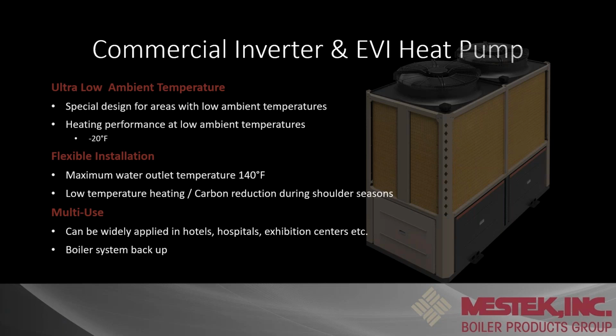It can be applied anywhere. It's basically just trying to match that load. It's going to depend on how many you will need, but hotels, hospitals, exhibition or exhibit centers, and we can also tie in a boiler as backup. I'm going to touch on that as well, but just think of these areas where they're saying, I have to reduce the carbon footprint. Does that mean you have to take the boiler out? No, that means we may add 2 or 3 heat pumps, and all of a sudden we're reducing carbon emissions. Keep that in mind as well. That doesn't mean we have to go all in, all heat pump. We may still want to use some high efficiency gas-fired boilers.